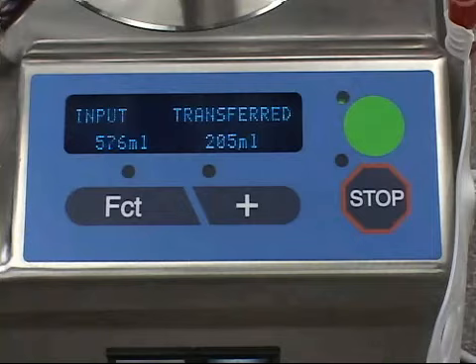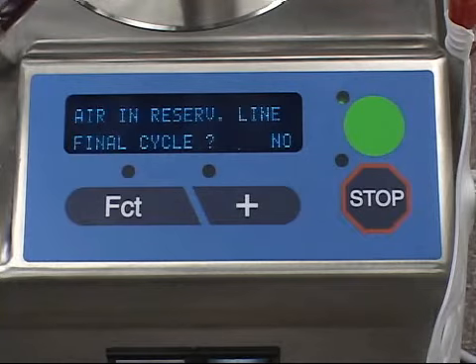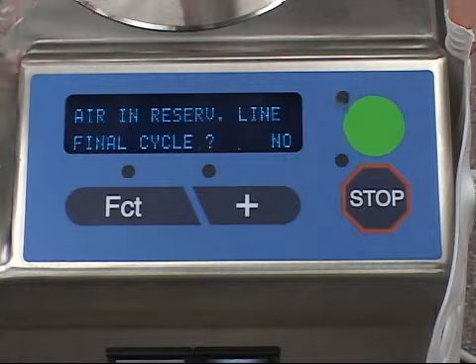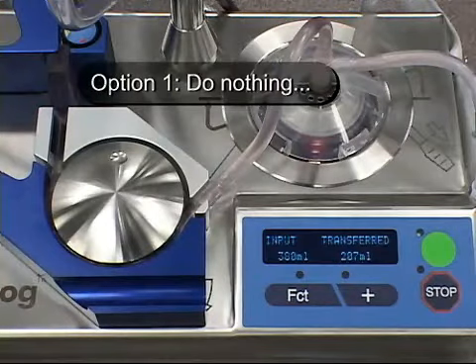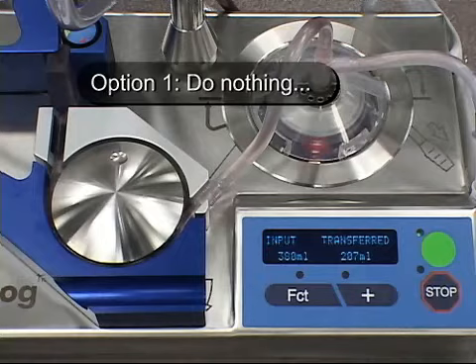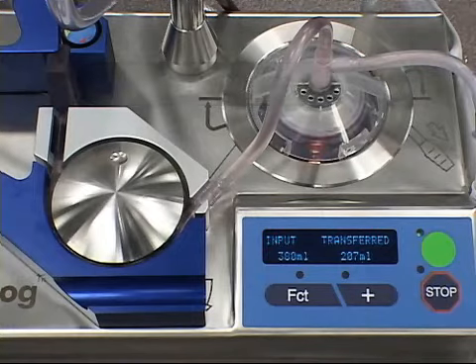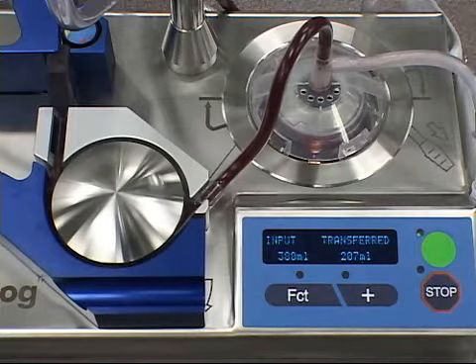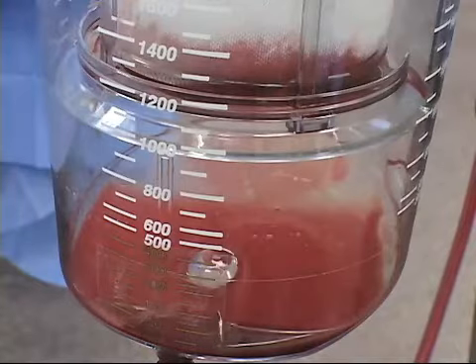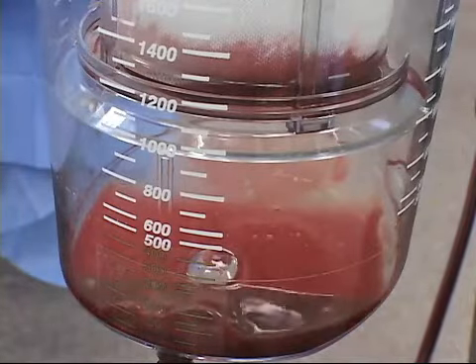If there is not enough blood in the reservoir to fill the bowl completely, the machine will stop during the fill phase and display the message "Air in reservoir line, final cycle, No." At this point, there are three options. Number 1. Do nothing. The centrifuge will continue to rotate for 1 minute, then it will stop. The contents of the bowl will automatically be returned to the reservoir, and the machine will start again when the blood volume is 800 milliliters.